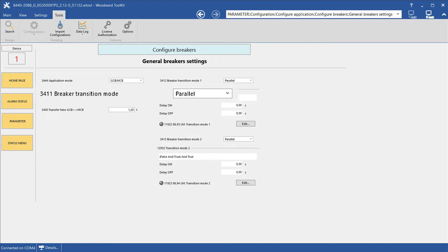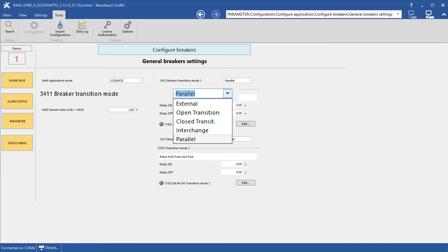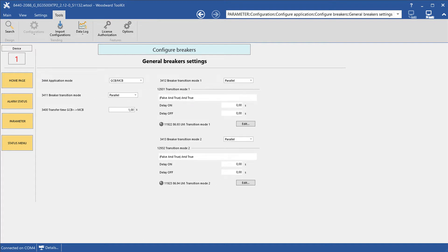As we are talking about the handling of two breakers in this video, we can choose between external, open transition, closed transition, interchange, and parallel. At parameters 3412 and 3413, you can define additional alternate transition modes activated by the corresponding logics managers.